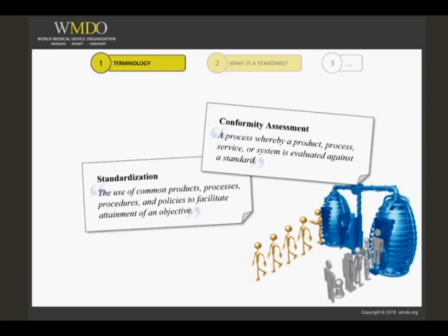In many industry sectors, particularly where safety is involved, conformity assessment is carried out by a third party, usually called a conformity assessment body. Conformity assessment bodies are frequently certified by some national certification organizations as being competent to carry out their assessment activities. In the medical device sector, that certification organization is usually the government ministry responsible for health and welfare. Examples are the notified bodies in Europe, who are identified and certified by the competent health authorities in each of the member states.